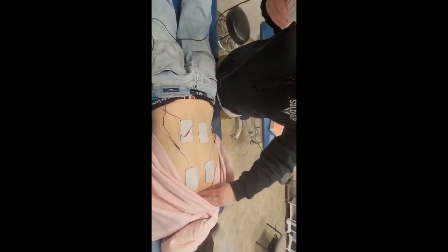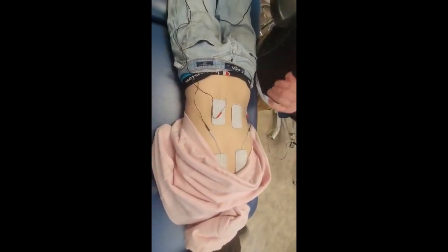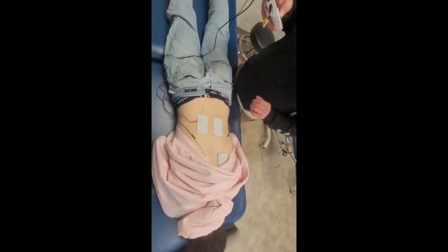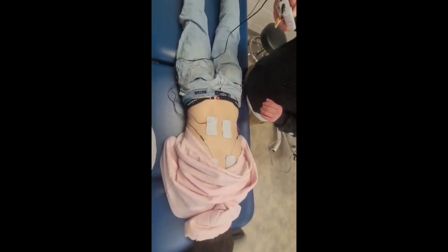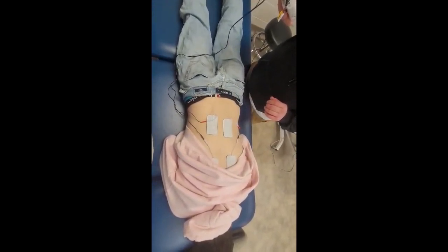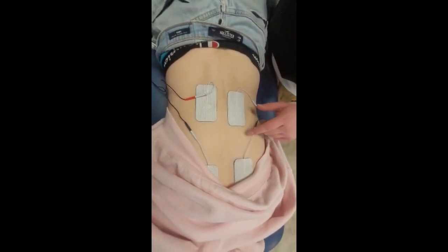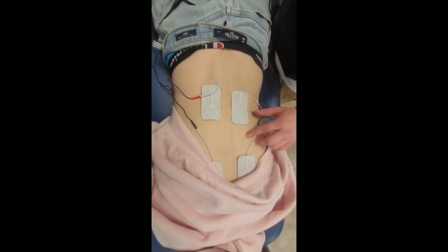Okay, so we're going to go ahead and show you guys the dual bipolar setup. So this is how you'll have the patient set up and laying on their stomach. So with dual bipolar, one channel will be on one side, the other channel will be on the other side. So I'm going to turn up channel 1, and again, do not pay attention to the numbers, just watch for that muscle contraction. Justin, let me know when you feel this. Okay, I'm seeing the muscle contraction, so once you see that muscle contract, then you're going to back down.